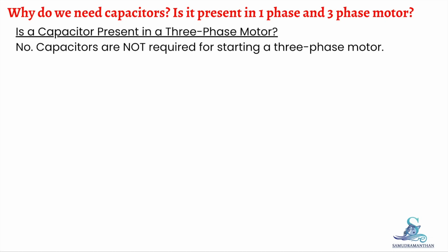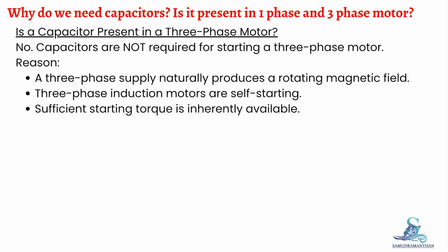No. Capacitors are not required for starting a three-phase motor. Reason: a three-phase supply naturally produces a rotating magnetic field. Three-phase induction motors are self-starting. Sufficient starting torque is inherently available.